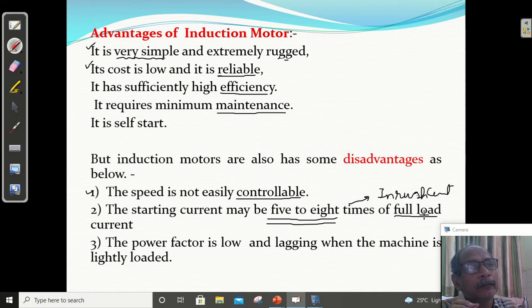We have a 3 HP motor. In India, it may take around 4.5 ampere. If we take a 5 HP motor, it will take around 1.5 times of 5, means 7.5 ampere current. Suppose we have a 10 HP motor, roughly it will take around 15 ampere at full load. Clear? So for a 3 HP motor कितना लेगा ये? 1.5 times मतलब 4.5 ampere full load current.